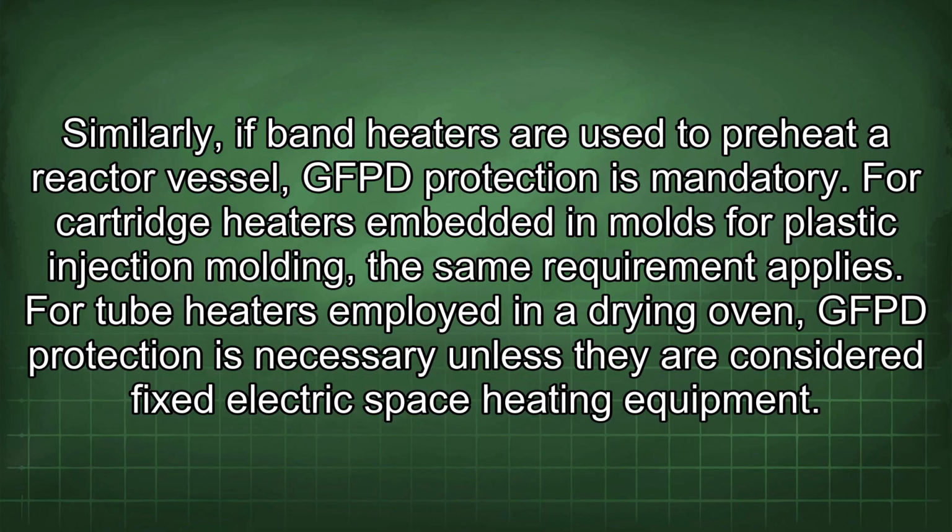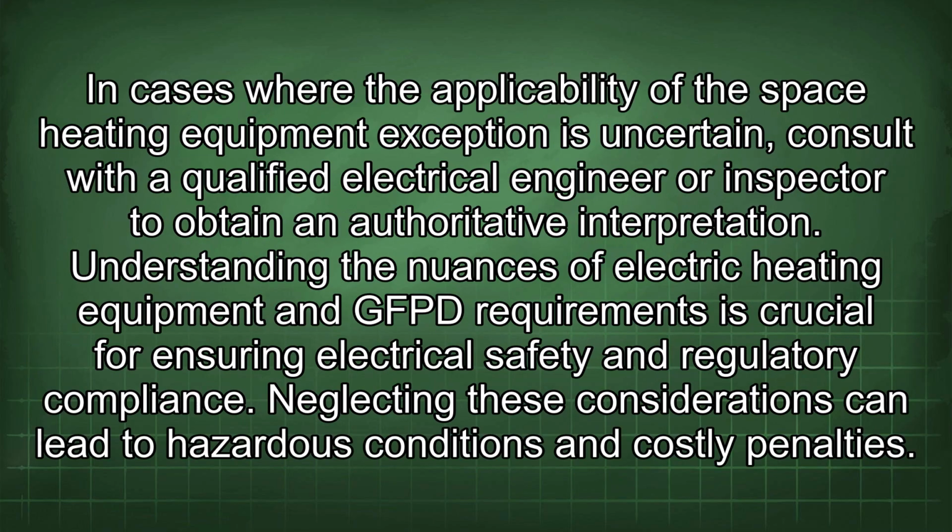For tube heaters employed in a drying oven, GFPD protection is necessary unless they are considered fixed electric space heating equipment. In cases where the applicability of the space heating equipment exception is uncertain, consult with a qualified electrical engineer or inspector to obtain an authoritative interpretation. Understanding the nuances of electric heating equipment and GFPD requirements is crucial for ensuring electrical safety and regulatory compliance. Neglecting these considerations can lead to hazardous conditions and costly penalties.